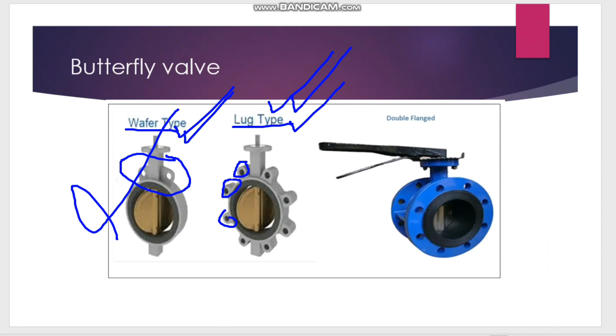I will show you the difference between lug type and wafer type. In this image you can see this is the wafer type and this is the lug type. They particularly mention that we must not use the wafer type, we must use only the lug type, because the lug type has plenty of flange holes like this, but the wafer type only has two arrangements. So they strictly mention that we have to use only the lug type butterfly valve for chilled water applications. Wafer type butterfly valve is not used for chilled water; it can be used in other applications.